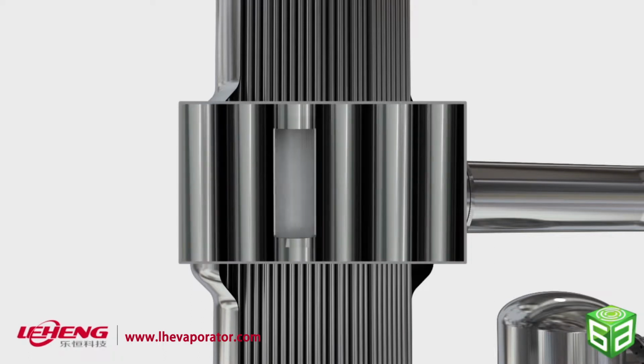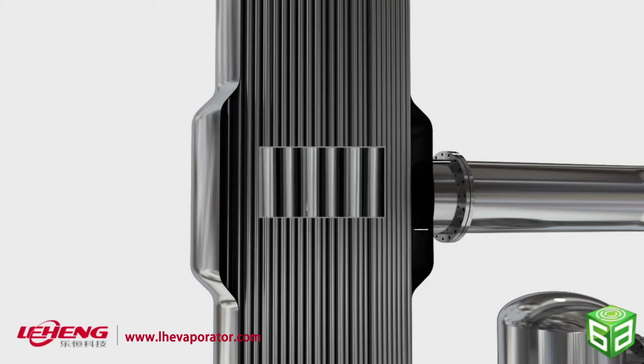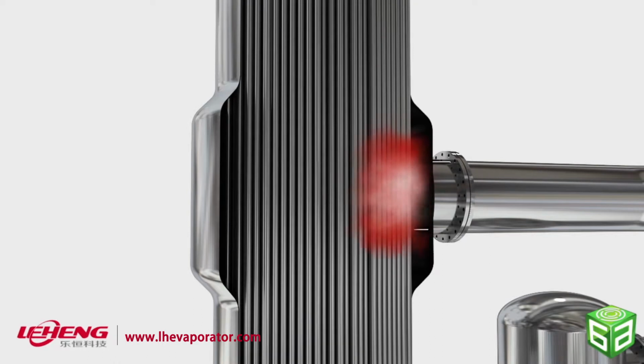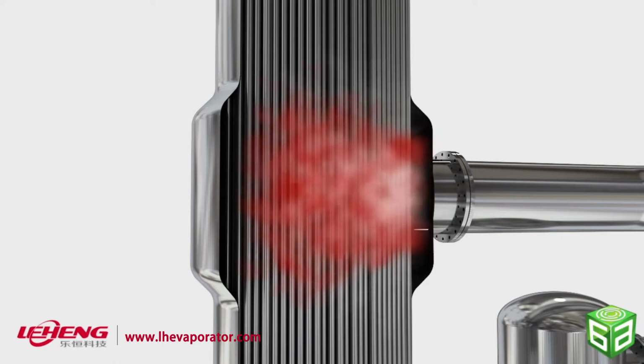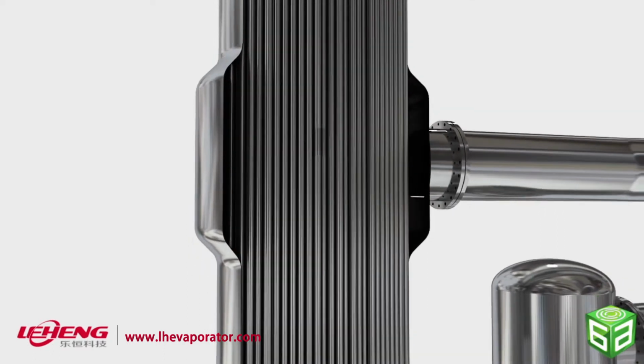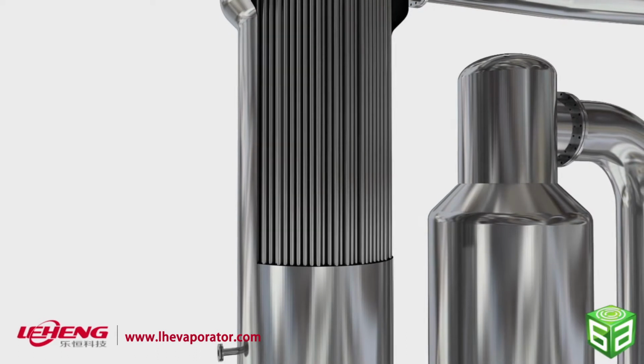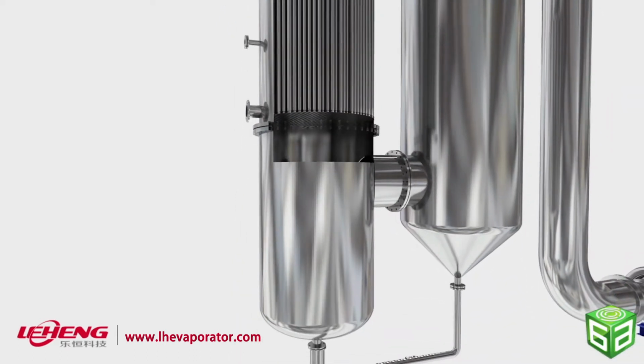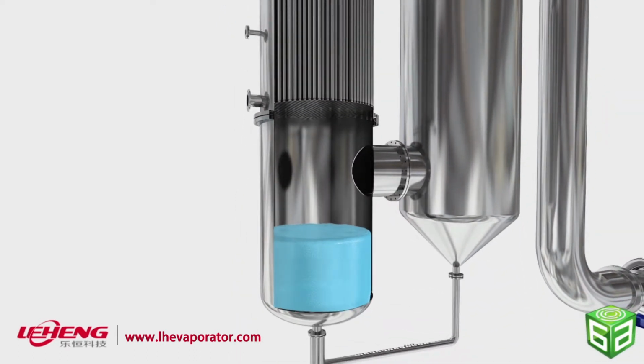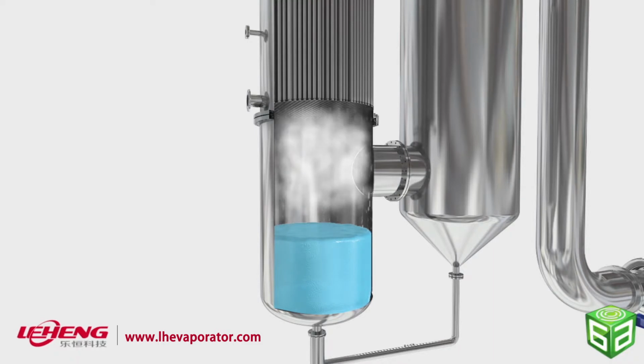Feed liquid forms a thin film layer on the inner surface of the tube and flows downward with the generated steam. Compressed steam from the compressor enters the heat exchanger's shell side. The temperature of the feed liquid in the tube increases and it starts boiling after reaching the evaporation temperature, due to heat exchange with hot steam on the outside of the tube.